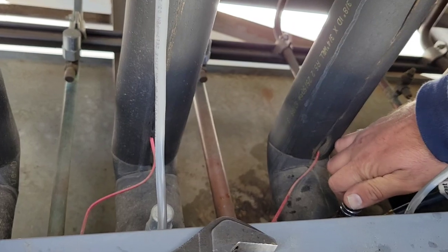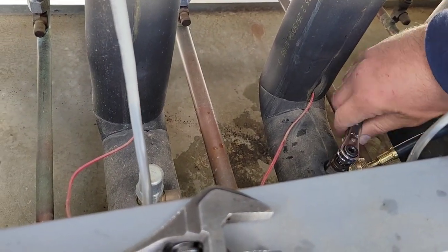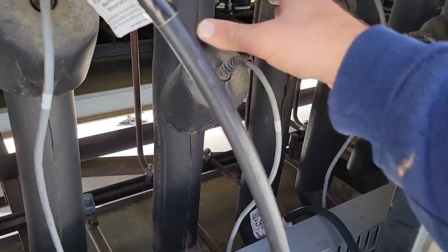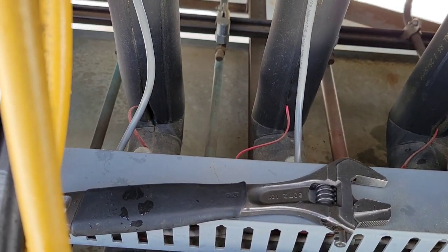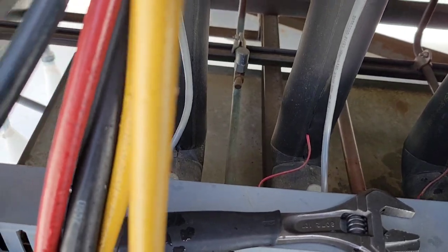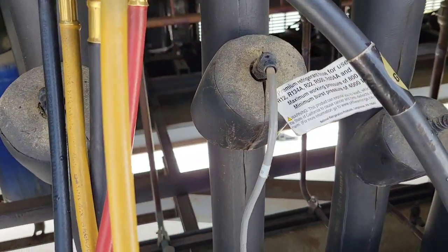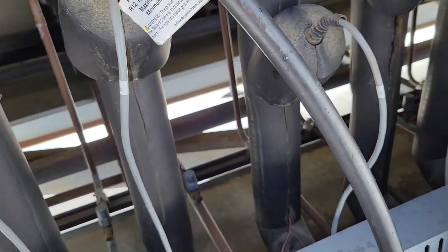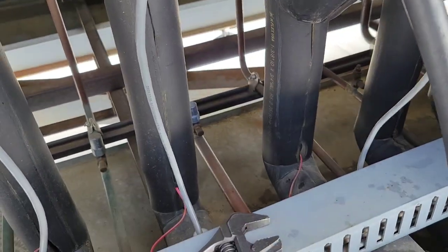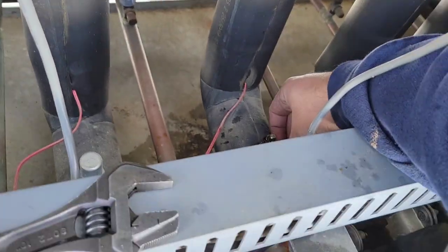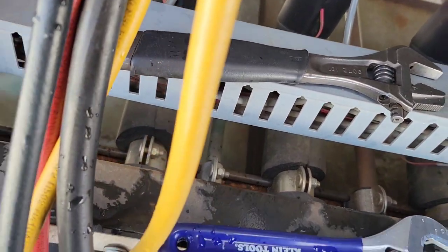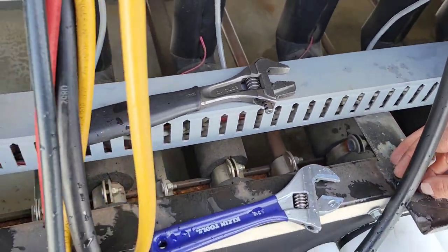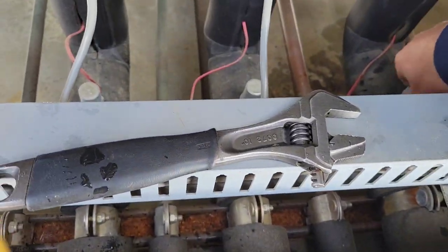So anyway, now we're going to go down and check the specific case. If it didn't have a CDS valve, this is a CDS valve, it's a type of EPR, evaporator pressure regulator, okay? If it had a liquid line solenoid, you would check that. Or if it had, let's say, a suction stop, you could check that as well. You just want to make sure the device that activates the flow of refrigerant is working correctly. So now we know that we have enough refrigerant, that our pressures are right, and that our device that sends refrigerant to the case is working. So we're going to now go down and check the case.